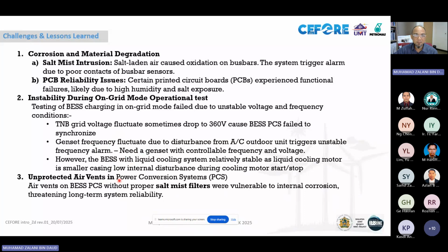And we found that some of the battery energy storage PCS designs come with unprotected vents. When we look inside the vent, they did not come with salt filters, so it is exposed to salt, which ends up with corrosion of the vent system.